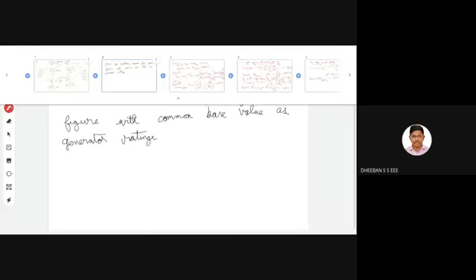Okay. And for this, Z per unit new of T4 will be equal to 0.08 into 100. So it is a base MVA of your generator 50 into 110 by 110. Okay, so this gets cancelled. This becomes 2. So finally we'll be getting j 0.16 per unit. And after this, again you're making a jump from your T4 primary to your T4 secondary. So you have to revise your kV. So a revised kV new of T4 will be equal to 110 into 11 by 110. So you'll be getting 11 kV.